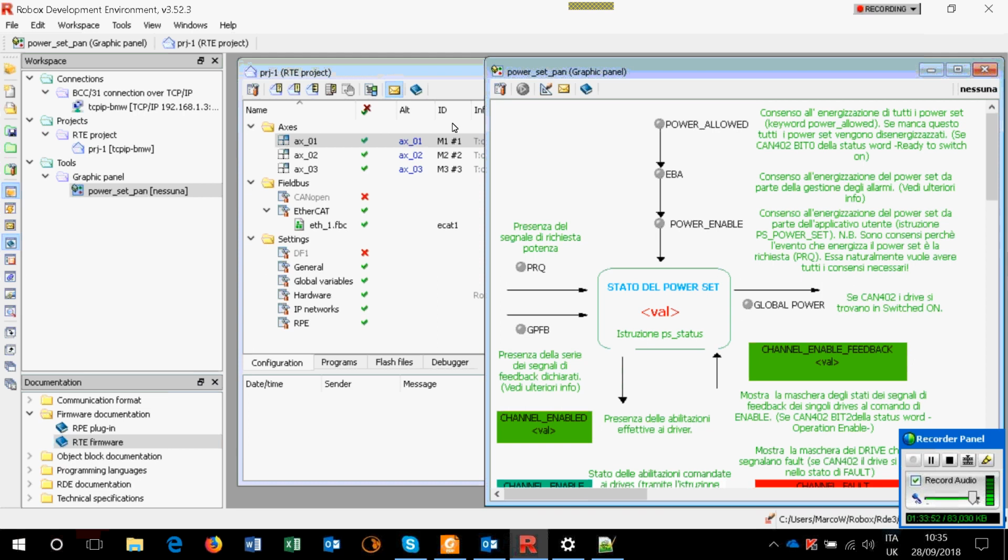Okay? When we have an alarm, the operating system, the RDE, will take out that bit, which is in the cascade of the enable of the system. Okay? This means that to have power, we must have all the 3 ones green, enabled. If at least one is not okay, power is not present. This is very important. So, main keyword: enabled by alarms, power enabled.